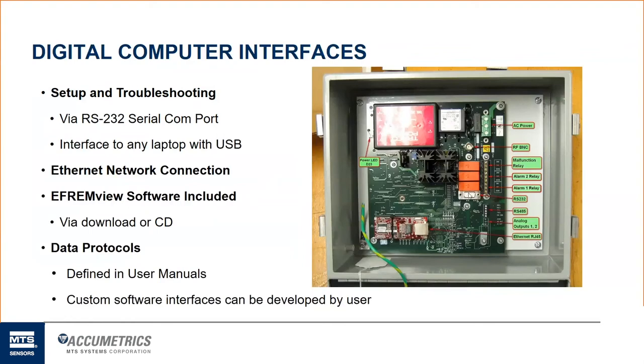That connects right to a laptop easily, where you've installed the EFREMview software, and that allows the user to adjust those field resistance thresholds of the warning and ground fault alarm, as well as change the speed at which that data transmission happens between transmitter and pickup. We usually recommend that customers leave that transmission data rate at about 10 seconds or more, just to eliminate any false positive readings. There's really no need for a faster measurement than about 10 seconds, because this is not going to be something quick. This is a long-term monitoring feature, where they're looking at that field resistance for a year or 2 years at a time.